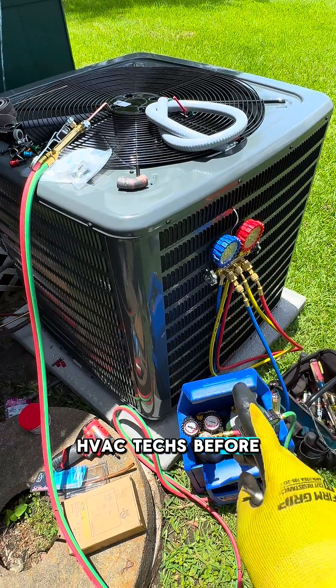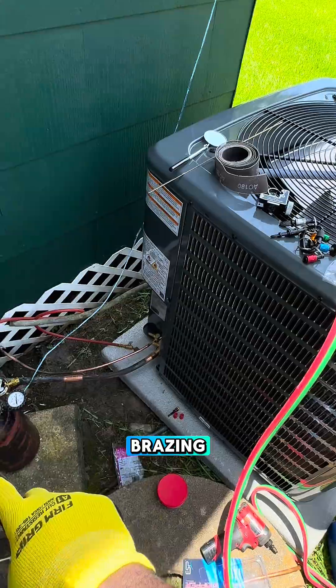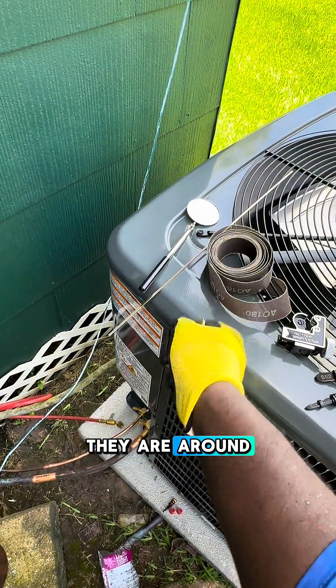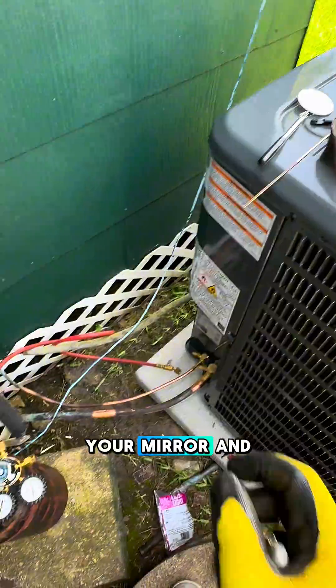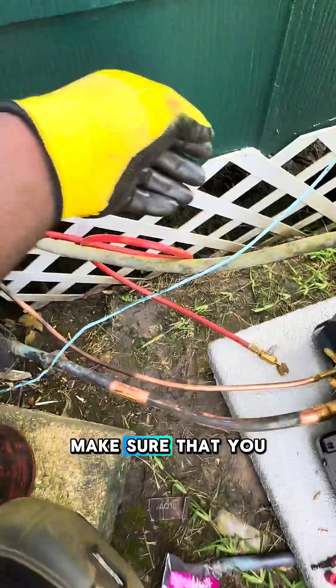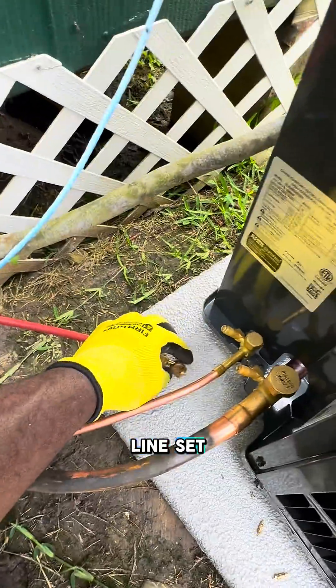HVAC techs. Before you open your torch, light it and start brazing, make sure that all the materials you need are around you, solder your mirror. And very importantly, make sure that you run nitrogen at 5 PSI through the line set.